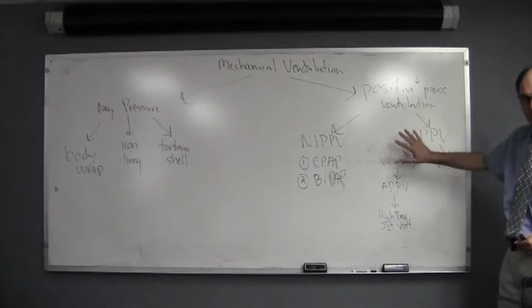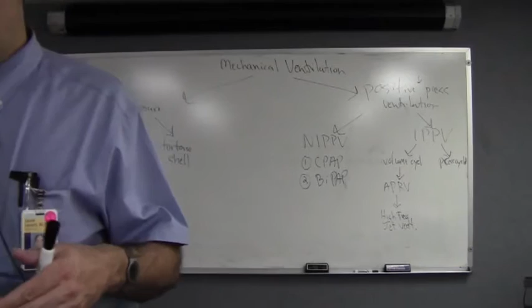Pressure cycled ventilation is another mode of ventilation that controls the pressure. You can set the pressure above which the machine will not go, the pressure within the airway system. So you set a drive pressure and then you add the PEEP to that. Okay? And those two pressures you add, and that gives you the total pressure.